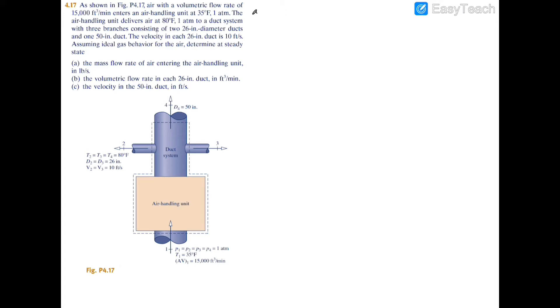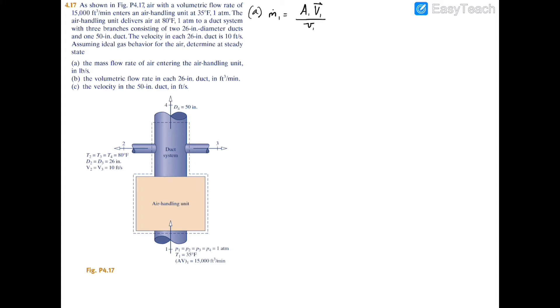For part A, we're looking for the mass flow rate at duct number one. At duct number one we can use the formula: mass flow rate at one equals the area at one times the velocity at one divided by the specific volume at one. Notice that the numerator is just equal to the volumetric flow rate, so we set that equal to 15,000 cubic feet per minute and convert to per second by dividing by 60.